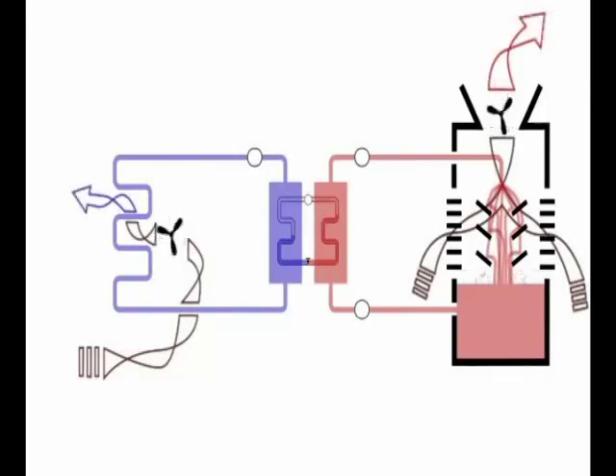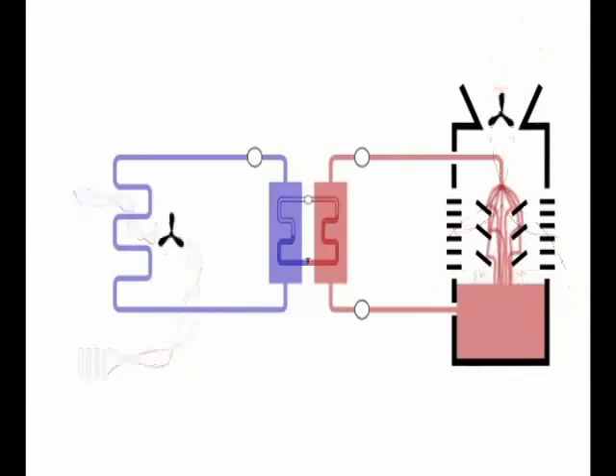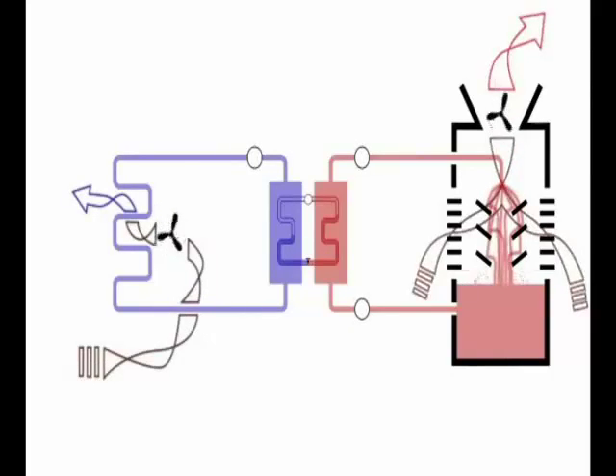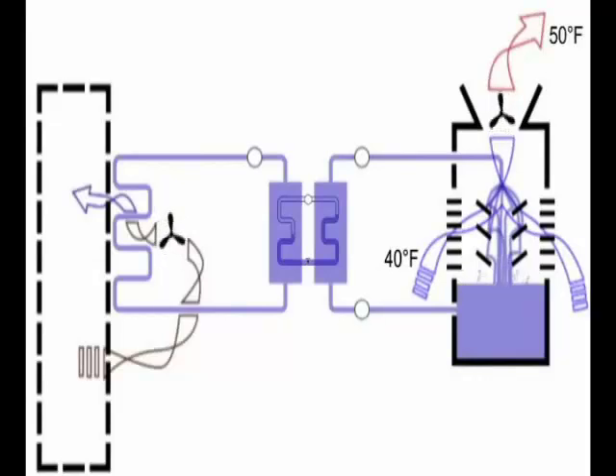When you do this, when you cool your buildings using the free cold found outside instead of the compression refrigeration loop, it is said that you are using the system in a mode called the economizer. Here, we'll review two methods of doing this, so-called free cooling: water side economizers and air side economizers. In a water side economizer mode, cold air cools, and it really cools because it's winter, the water in the cooling tower. That cold water moves to the condenser side of the chiller and cools the coolant.